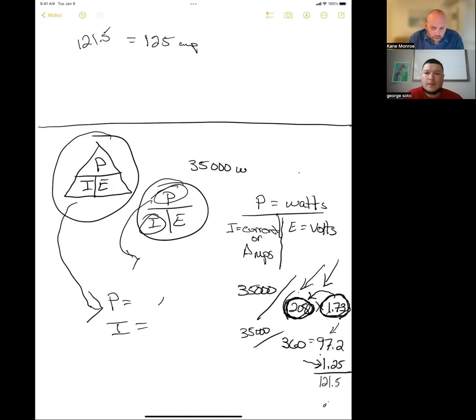So, going back to this motor, or this transformer, the 208 side. We did all the math down here and we came up with 121.5, but they don't make a breaker that size. Right, so you're going to have to run it up to 125 amps.